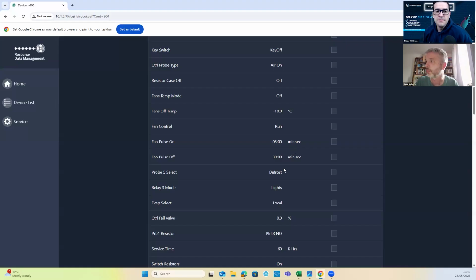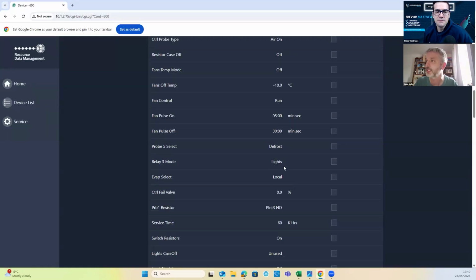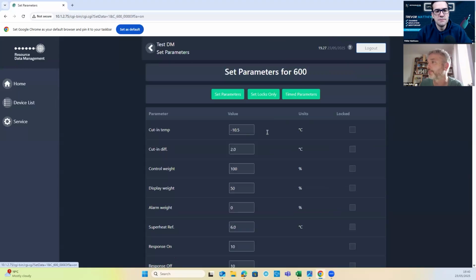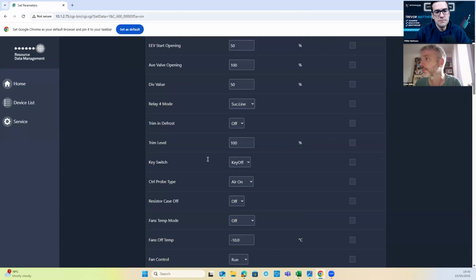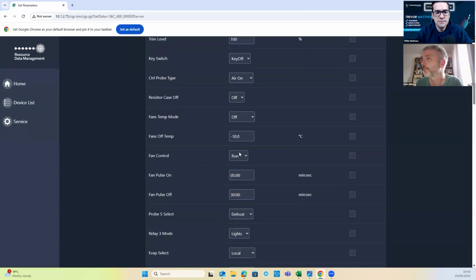You can tell it what Probe 5 does. In this case, it's defrost. You can set it to be monitoring as well. You can tell it where the lights are. This is where you tell it, how am I sensing my evaporating temperature? Yeah. So if we have a little look at what's in that, because that's an important one. Evap select, which is right there.